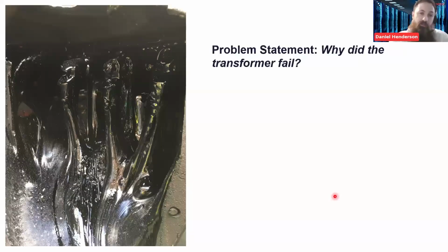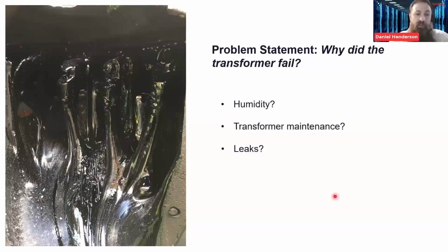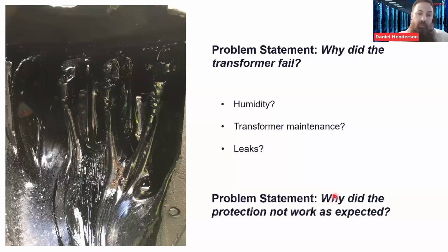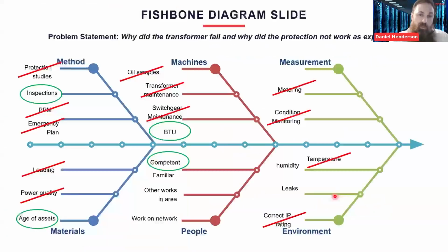The transformer was the area that failed, but there's nothing left. You can get some really good outputs from forensic investigation, but essentially the feedback I was given was that it possibly could have been humidity, could have been linked to your maintenance activities, could have been from leaks, but because there's nothing left, it's very difficult to identify what that is. For the age of the asset, could that have been linked to it? Obviously, we've covered a lot of things that could have been. I think the big thing for me, from a safety perspective, is why that protection did not work as expected.